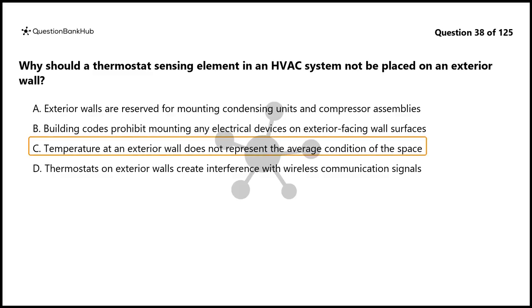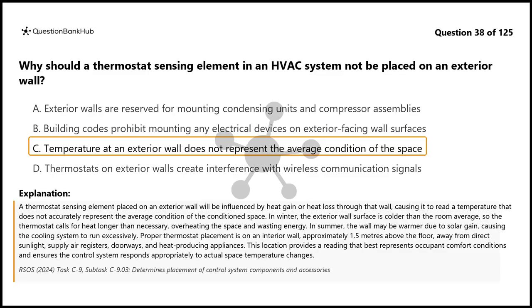The correct answer is C. A thermostat sensing element placed on an exterior wall will be influenced by heat gain or heat loss through that wall, causing it to read a temperature that does not accurately represent the average condition of the conditioned space. In winter, the exterior wall surface is colder than the room average, so the thermostat calls for heat longer than necessary, overheating the space and wasting energy. In summer, the wall may be warmer due to solar gain, causing the cooling system to run excessively.